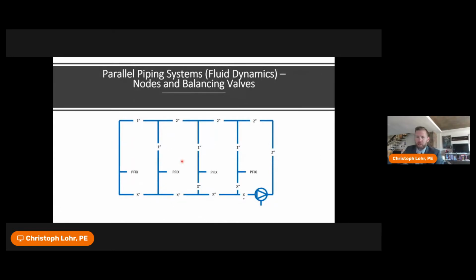We have a larger loop. Now we have 4 parallel branches. Again, nodal points are those points where the flow can diverge in a closed state condition. Also where pipe size changes, and also where you go from a supply side to a return side of the system. In order to get the flow from our water heater and recirculation pump in the mechanical room all the way out to our furthest point, assuming this is to scale, we have to add balancing valves to each one of those branches.